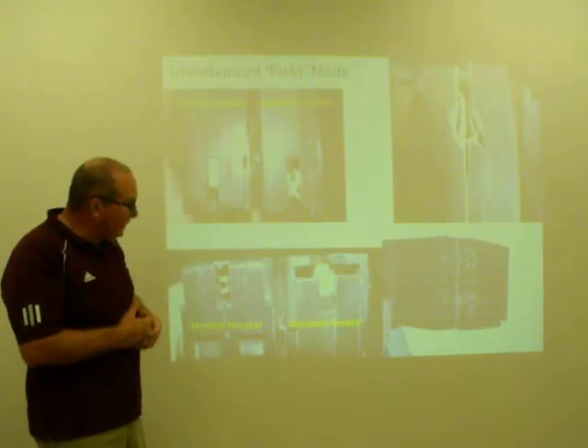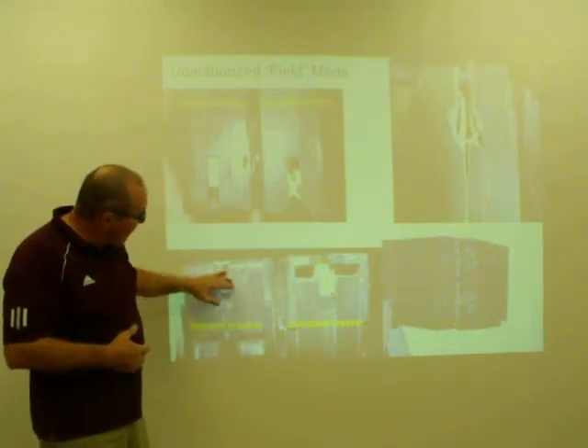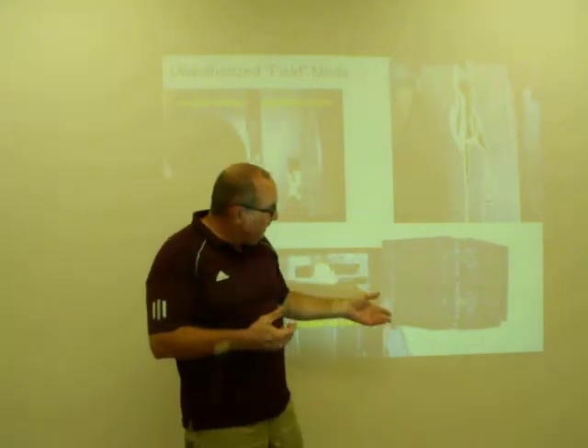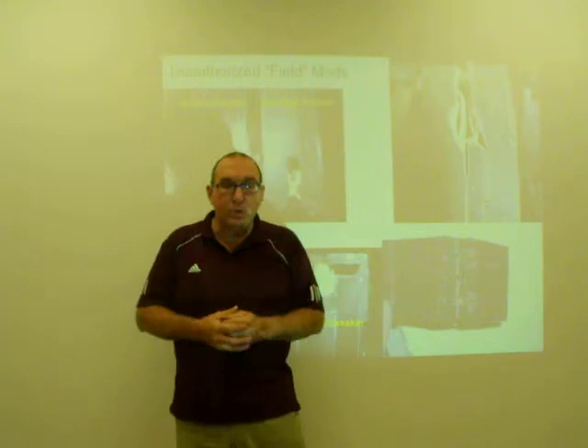Conversely, with different brands here, you see a slightly different variation, as I showed you with these two breakers, where the tandem breaker does not have these two slots. The standard breaker does, or vice versa, depending on the brand. So again, a little work with some pliers or a screwdriver or something, and they modify the molded case to make the breaker fit.